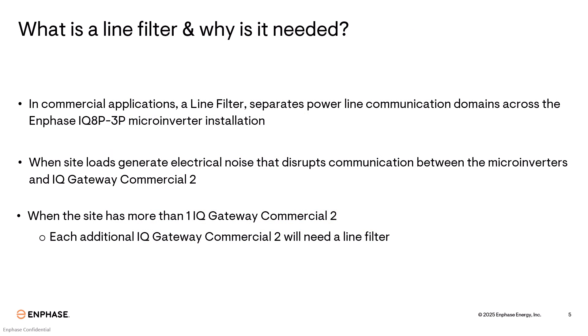You will also need a line filter if your site has more than one IQ gateway commercial two. Each additional IQ gateway commercial two will need a line filter. So if your site has two IQ gateway commercial twos, you'll need one line filter. If your site has three gateways, you'll need two line filters and so on.